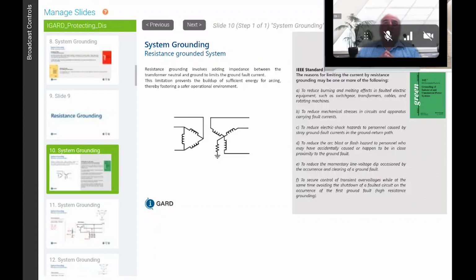So where do we want to limit or protect our system with a high resistance grounded system? For all these reasons, every location that I've been to has the benefit of employing a resistance grounded system. So we put them in petrochemical facilities where you can't tolerate an unplanned shutdown, data centers, and pulp and paper facilities. In Canada, we put them a lot in banks.